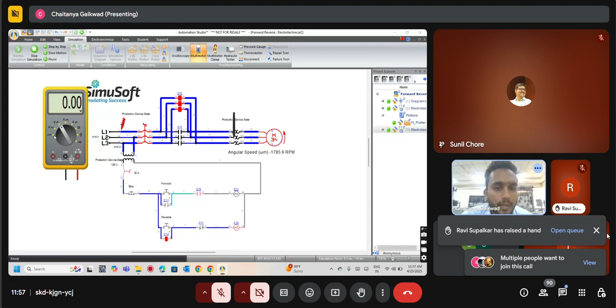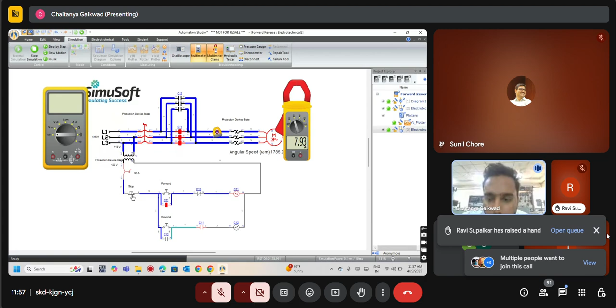I will now stop the motor. My current is 0. When I start the motor again in the forward direction, the current increases and then gets constant at 7.93, or about 8 amperes. This is because there is a high inrush current in this motor, which we can also see in our plotters and all.